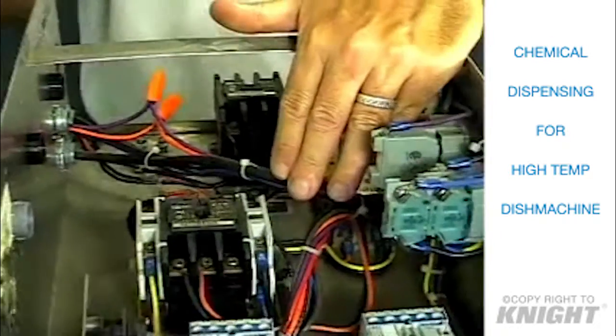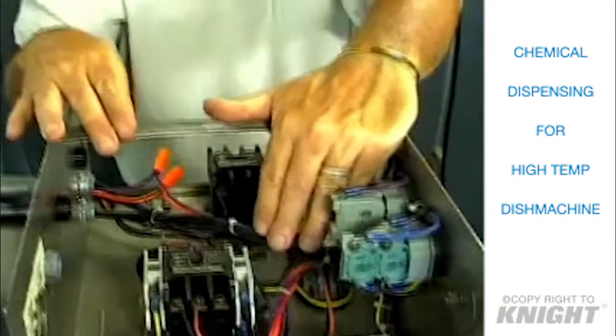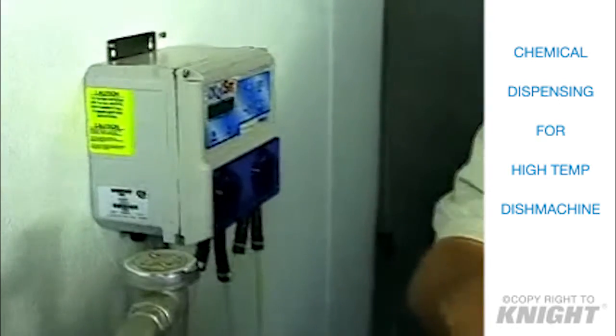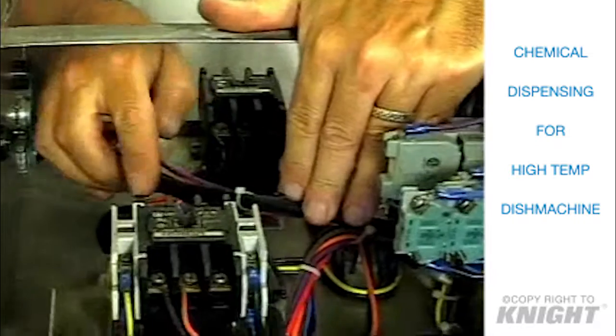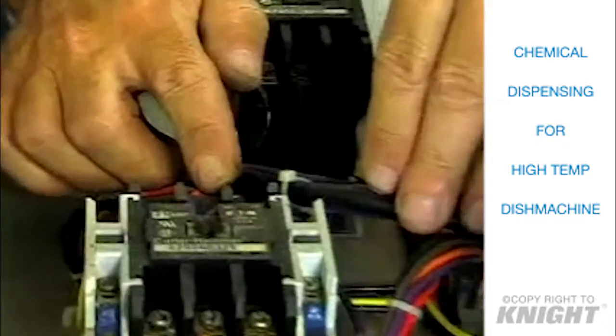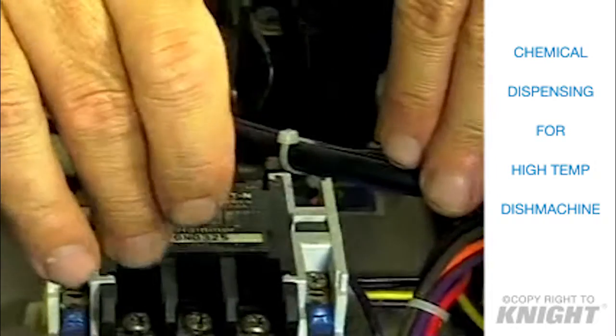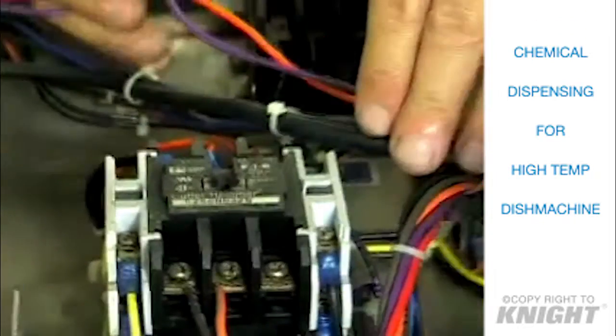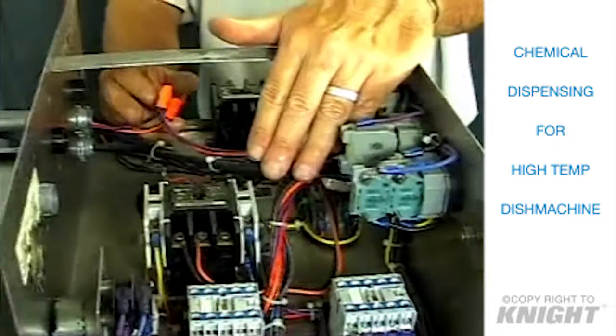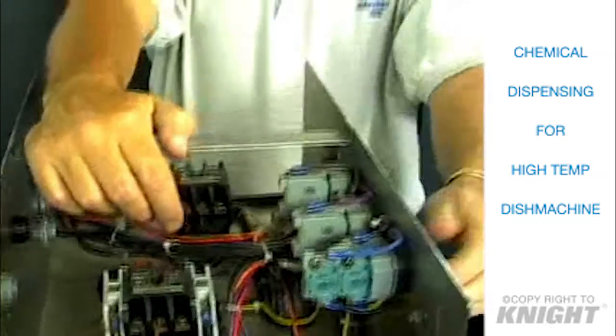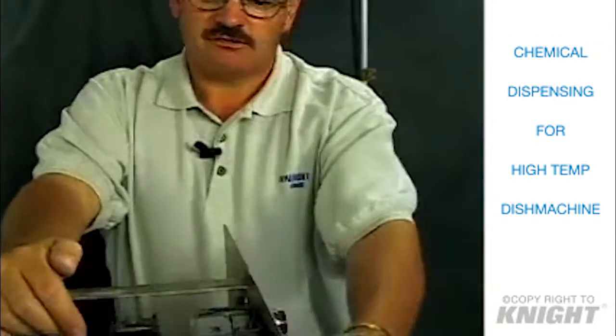Now, if I want to hook this machine up as a probeless operation, I'll make all the conversions in the Digiset or the MicroPro, as I always do. And I will power the dispenser from line 1 and line 2, just like I do for probe. I no longer require my connection for T1 and T2. I'll just hook up the orange and purple wire to my rinse signal. And when the machine goes through its initial fill, I'll turn the switch on.